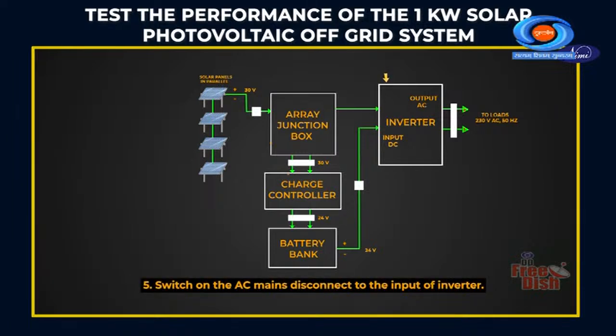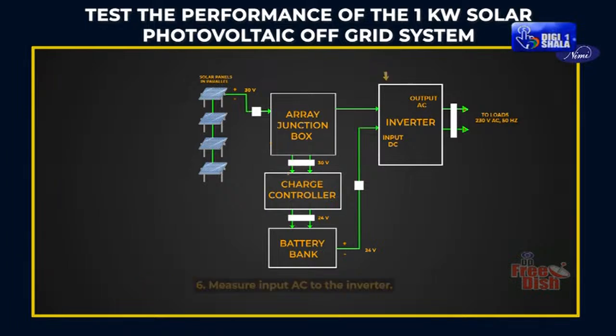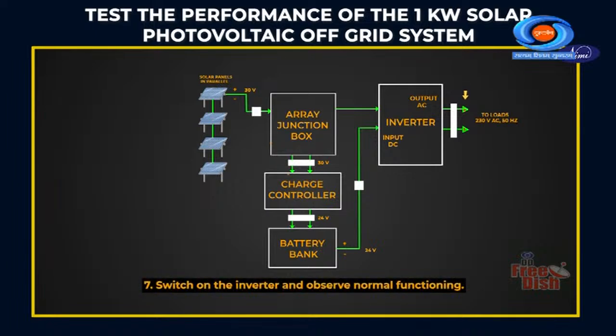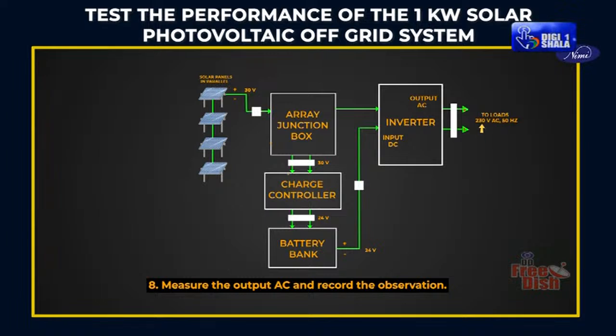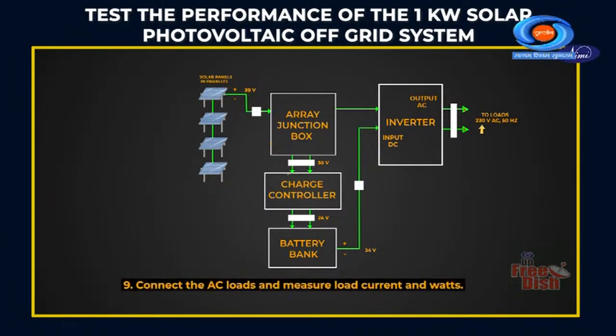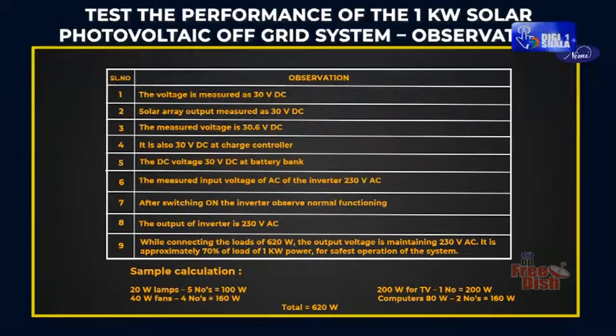Switch on the AC mains disconnect to the input of the inverter. Measure input AC to the inverter. Switch on the inverter and observe normal functioning. Measure the output AC and record the observation. Connect the AC loads and measure load current and watts.